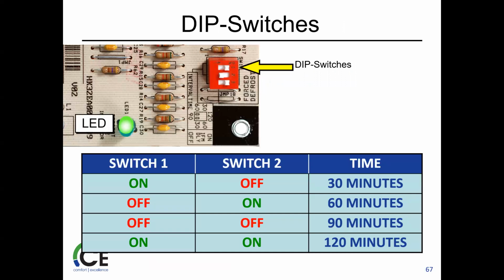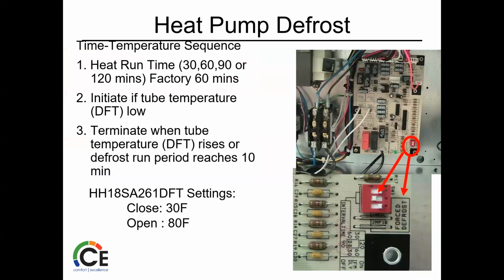That's how long it's going to wait to defrost, right? That's the huge thing. Doesn't mean it's going to do it for 30 minutes. It just means it's going to wait to check if it needs it for 30 minutes. So depending on what you got going on there, most guys do that backwards. If they want more, they try and set it for 120 and they're going backwards. So same thing on a commercial unit as a residential unit. Yeah, that's what we talked about. Heat run time, factory 60 minutes. Just means it's going to run that long until it looks to defrost.